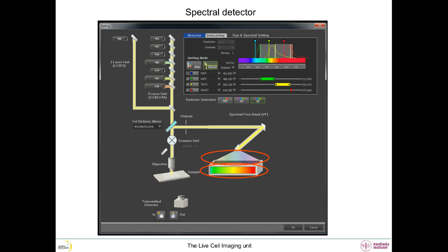In front of this rainbow, instead of the 4 detectors as in the previous example, we now have a spectral detector. A spectral detector is often an array of 32 detectors. Each of these 32 detectors receives only part of the rainbow. We can now decide which part of the rainbow goes to which detectors. For example, we can narrow down the green filter, and we can make the red filter wider to better match the fluorophores. This way, using a spectral detector can be compared to using virtual emission filters instead of physical emission filters. Using virtual filters is a powerful way to match emission filters and fluorophore spectra. However, you must remember that when you set the emission filter to be very narrow, only few photons will reach the detector, so very narrow filters can only be used with very bright fluorophores.